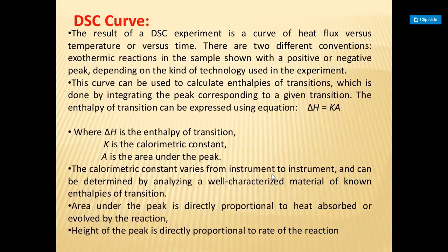Let us discuss the DSC curve, which is very important when discussing the differential scanning calorimeter. The result of a DSC experiment is a curve of heat flux versus temperature or versus time. There are two different conventions: an exothermic reaction in the sample is shown with a positive or negative peak, depending on the kind of technology used in the experiment.